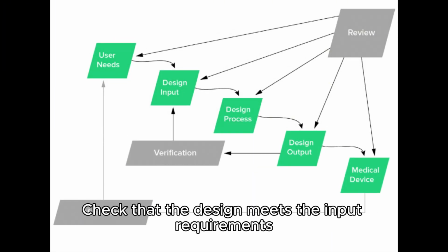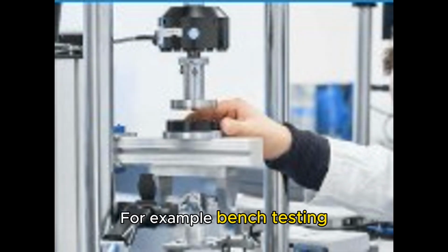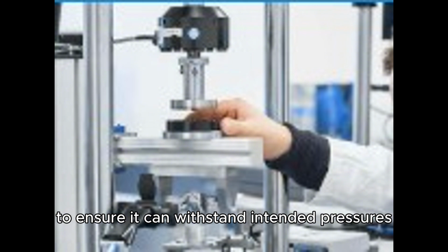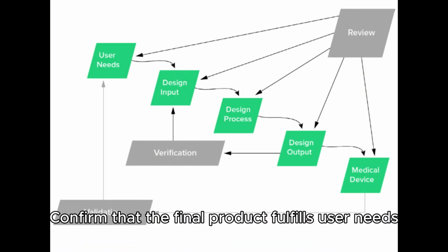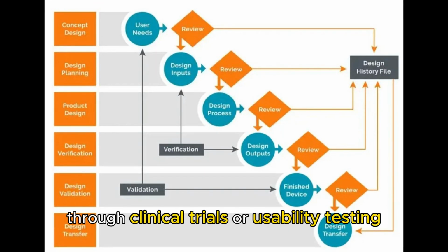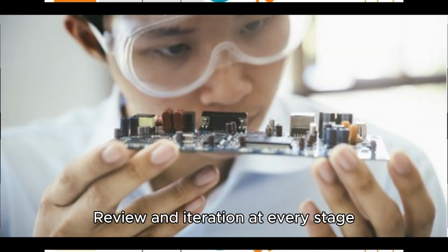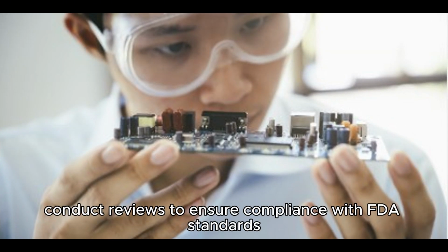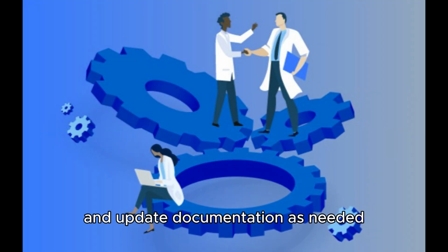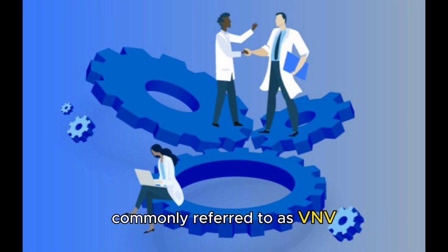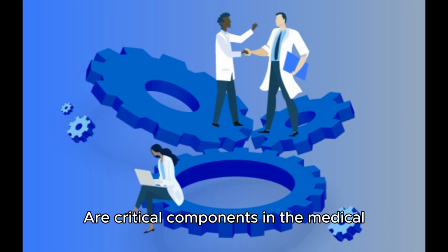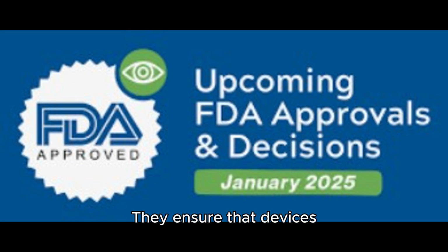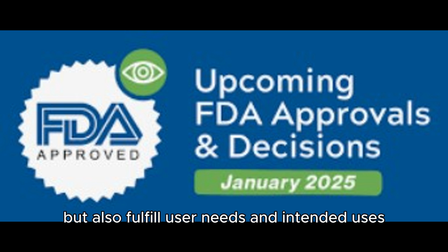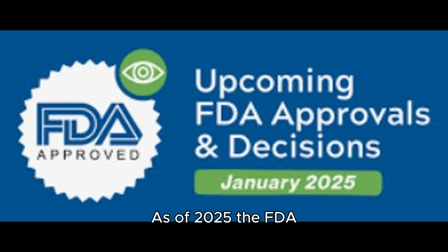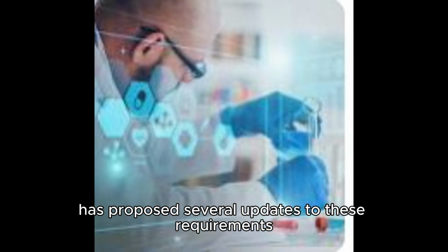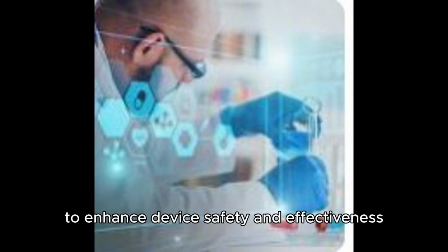Verification, check that the design meets the input requirements. For example, bench testing a catheter to ensure it can withstand intended pressures. Validation, confirm that the final product fulfills user needs through clinical trials or usability testing. Review and iteration, at every stage, conduct reviews to ensure compliance with FDA standards and update documentation as needed. Design verification and validation, commonly referred to as V&V, are critical components in the medical device development process. They ensure that devices not only meet design specifications but also fulfill user needs and intended uses. As of 2025, the FDA has proposed several updates to these requirements to enhance device safety and effectiveness.